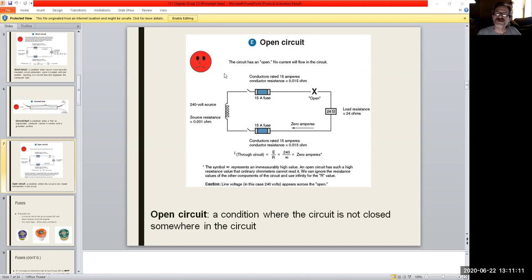And then we look at something called the open circuit. Now the open circuit, simply, there's nothing happening here. You're literally getting 0 amps, and this is a dead giveaway for you. If you have to troubleshoot a situation like this, you go out to where your device is located and read across it. You have literally 0 amps. You go back here, you see your voltages are there. It's like, okay, what's happening here? Well, by basic troubleshooting, you'd find out very quickly that you have a break in your line somehow. And again, what is this going to involve?